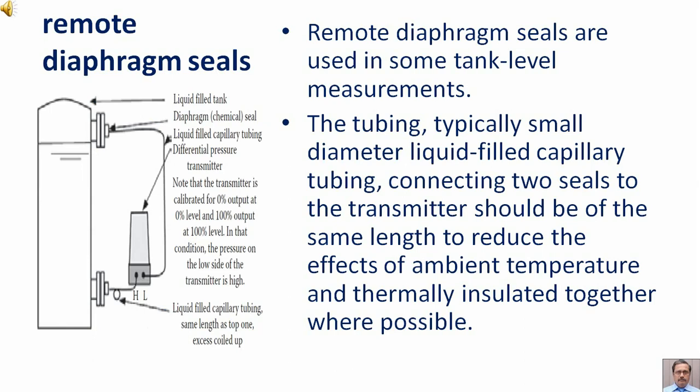Remote diaphragm seals. Remote diaphragm seals are used in some tank level measurements. The tubing, typically small diameter liquid filled capillary tubing connecting two seals to the transmitter, should be of the same length to reduce the effects of ambient temperature and thermally insulated together where possible.